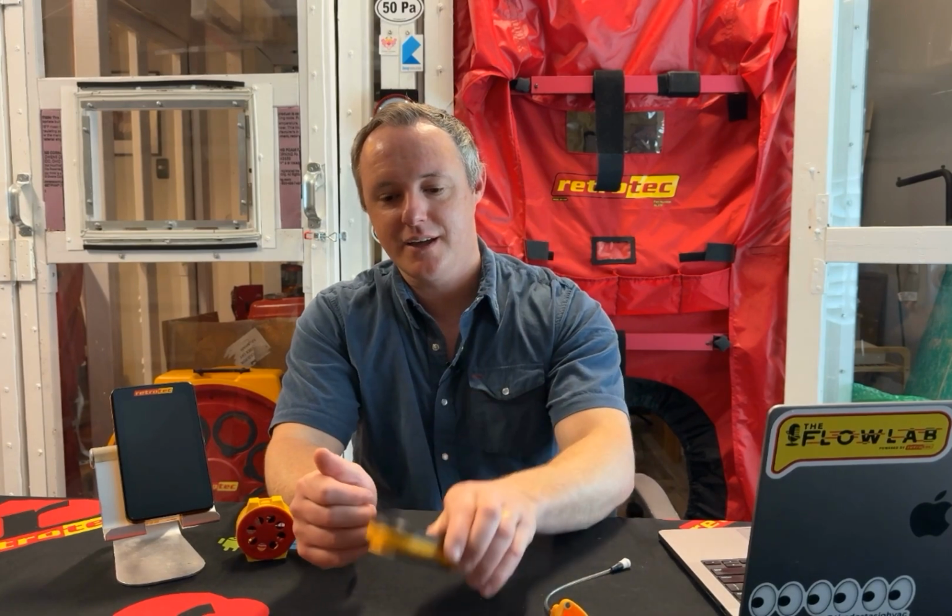And the other thing to think about here is if you're not getting pressure uniformity whenever you do that initial check with your second manometer, I would be offering my services to that builder to figure out why. That attic assembly should be tighter than it is. So usually when I get into a situation like this, if I'm testing a building and it's not coming out how the builder or the client wants it, that's when we start doing an hourly rate to see why that building isn't performing the way we want it to.